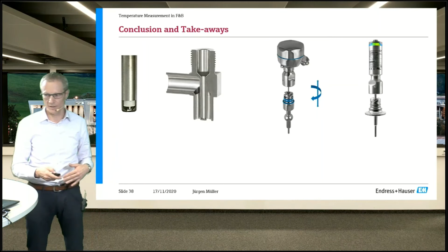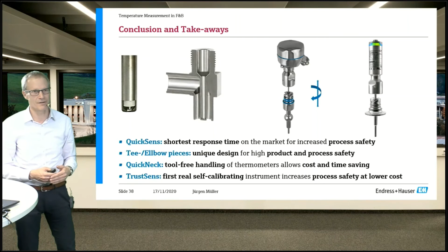The QuickNeck, which you can use either with our modular thermometers or also with a TrustSens, allow you tool-free handling, which in the end saves cost and time, especially when it comes to the point of doing calibrations. And finally, of course, the TrustSens, this unique and very innovative thermometer that does the self-calibration, and it is really a real calibration, and it's not just a verification of the temperature that it measures. So you don't just compare the value that the TrustSens measures with another temperature, with another thermometer. So you really do a real calibration at 118 degrees. With this, again, you improve your process safety at reasonable cost. And all the conclusions that I made and the takeaways that I mentioned are listed here, and you will also find that in the handout, of course.